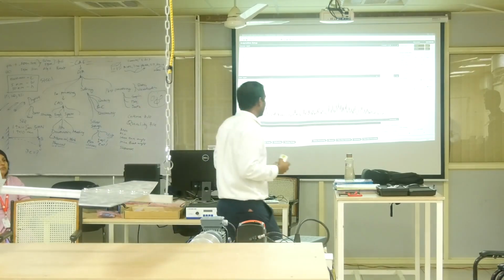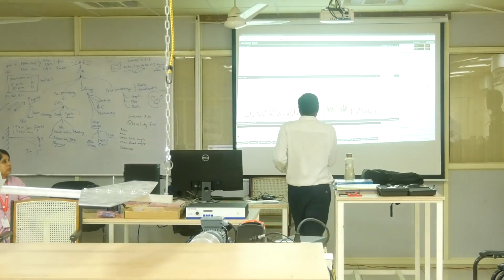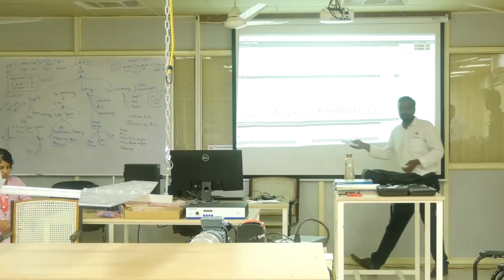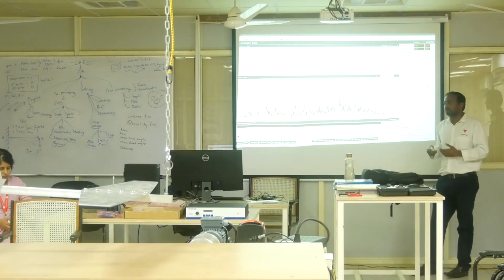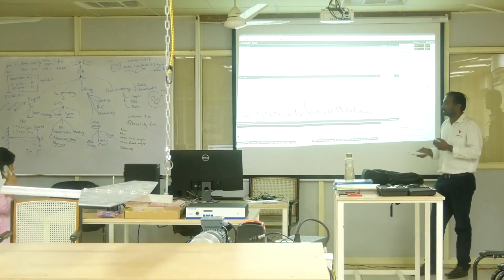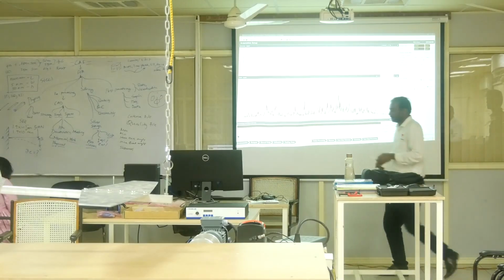So based on your calibration, it will properly set the range. And the purpose of giving this range is we should always measure the data within proper ranges so that we can avoid the cumulative errors that we are going to capture.